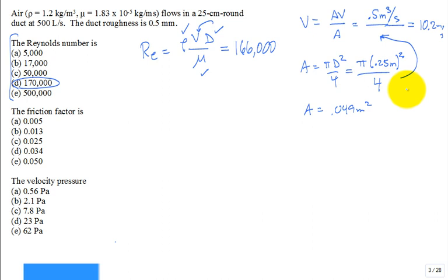Oh, no. Okay, now that we have the Reynolds number being about 167 or 166,000, what is the friction factor? This is the first time that you would need to use that duct roughness of a half a millimeter. And yes, the diameter is 25 centimeters. That's the diameter.